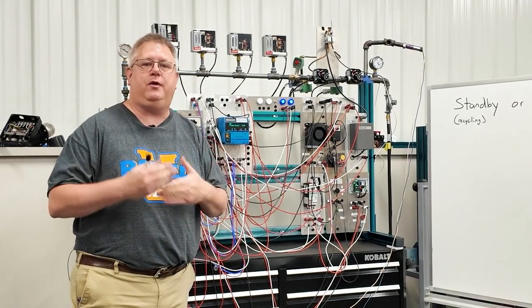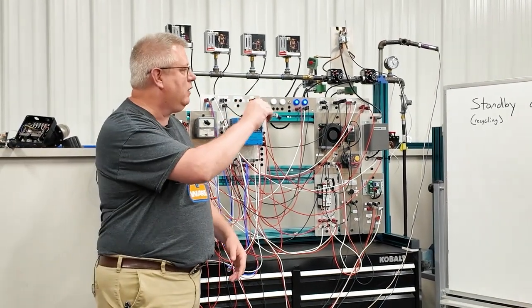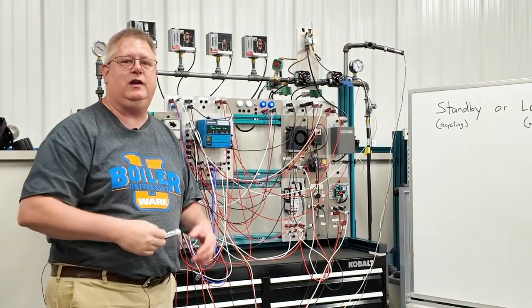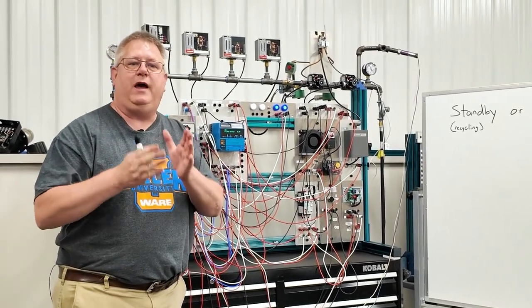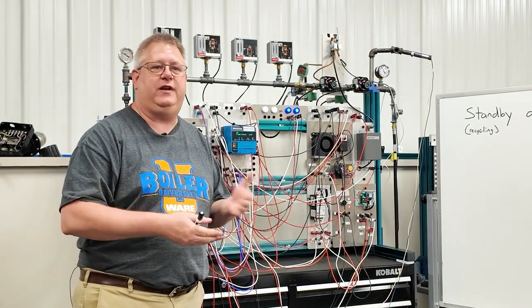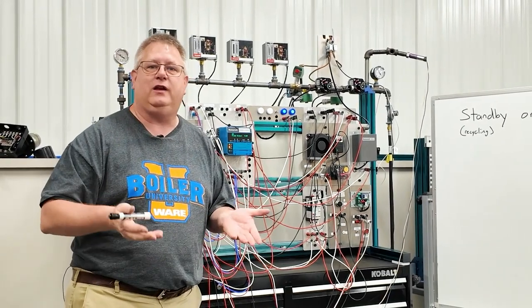So if we simply trip the boiler on each individual limits and kind of make a laundry list of what response we get to each limit trip, then we'll basically have a cheat sheet for the future. So when we're down on a particular limit string, we at least know which switches we can check.